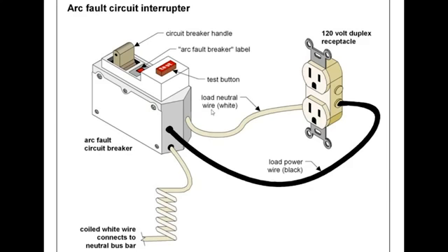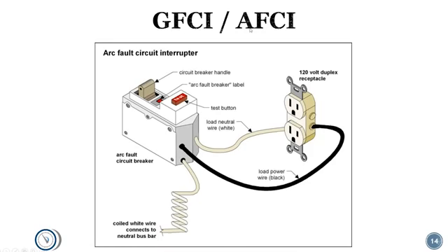And this is important when you're working with extension cords and that sort of thing, which comes up a lot in the trade. GFCIs really will help protect you because, again, you can create a path to ground that's enough to electrocute you but not enough to trip a breaker. A GFCI monitors the difference between what's going in and going out, and if it sees an imbalance, then it knows that there's some leakage to ground and it can trip. Arc fault's a newer thing. I just don't want you to confuse it with GFCI. Arc fault actually uses a circuit board inside the breaker that looks at the possibility of arcs. If it sees a signature that looks like there's an arc in the circuit, then that will trip the breaker. That's more for bedrooms, that sort of thing, to help prevent fires. So, GFCI is there to help protect you from being shocked or electrocuted. AFCI is there to help prevent things from burning down. So, sort of different functions.